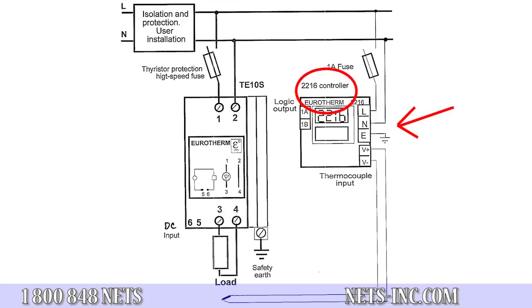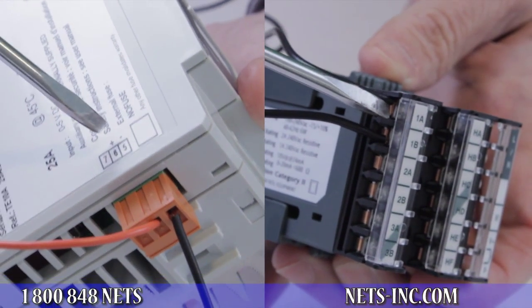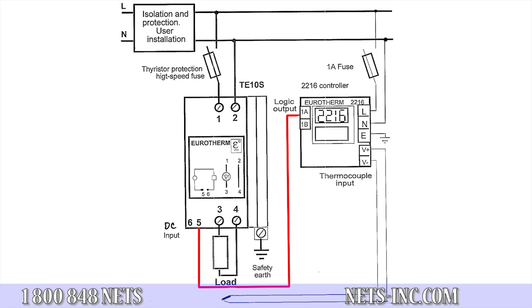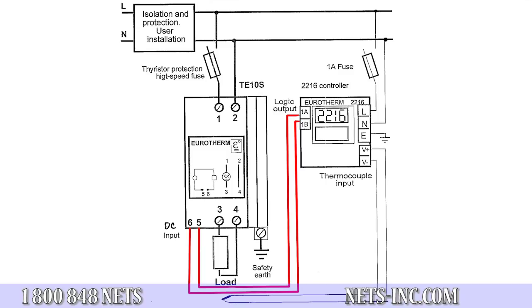In the wiring diagram shown, we are using a Eurotherm 2216E temperature controller and a Eurotherm TE10S power controller with a DC logic input command signal. First, wire terminal 1A positive of the temperature controller to terminal 5 positive of the power controller. Next, wire terminal 1B negative of the temperature controller to terminal 6 negative of the power controller. This completes the output wiring for this style of control. Now when the temperature controller turns on or off, the DC logic output produces a 12 volt DC signal to the input command of the power controller, and the power controller will turn on to allow current flow to the heating element.